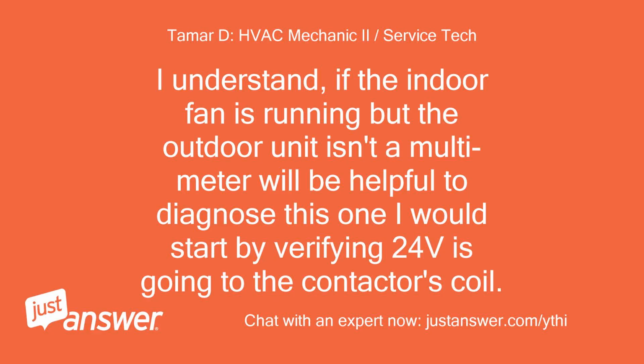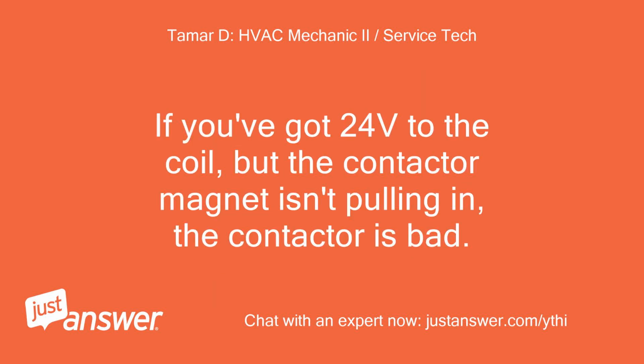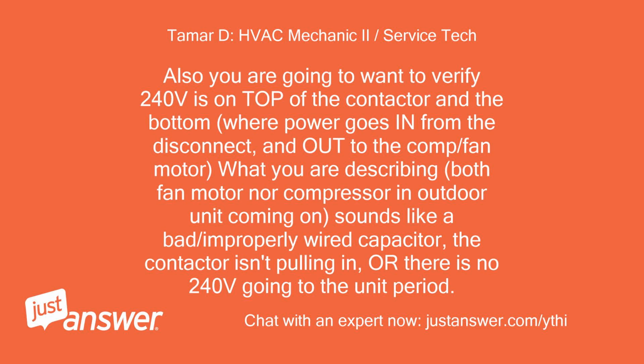I understand. If the indoor fan is running but the outdoor unit isn't, a multimeter will be helpful to diagnose this one. I would start by verifying 24 volts is going to the contactor's coil. If you've got 24 volts to the coil, but the contactor magnet isn't pulling in, the contactor is bad. Also, you are going to want to verify 240 volts is on top of the contactor and the bottom, where power goes in from the disconnect, and out to the compressor and fan motor. What you are describing, both fan motor and compressor in outdoor unit not coming on, sounds like a bad or improperly wired capacitor. The contactor isn't pulling in, or there is no 240 volts going to the unit, period.